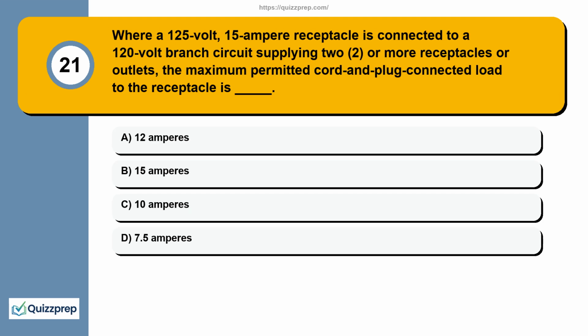Question 21. Where a 125 volt, 15 ampere receptacle is connected to a 120 volt branch circuit supplying two or more receptacles or outlets, the maximum permitted cord plug connected load to the receptacle is: 12 amperes, 15 amperes, 10 amperes, 7.5 amperes.